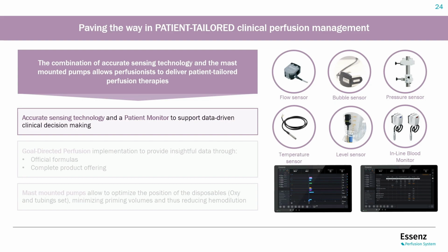The Essenz perfusion system is equipped with an accurate sensing technology: a new accurate and lighter bubble sensor, a new level sensor, flow sensor for both the centrifugal and the roller pump, and pressure sensors. We have also a brand new accurate inline blood monitor to allow the perfusionist to quickly react to patient metabolic needs. Moreover, the patient monitor supports you in data-driven clinical decision making.